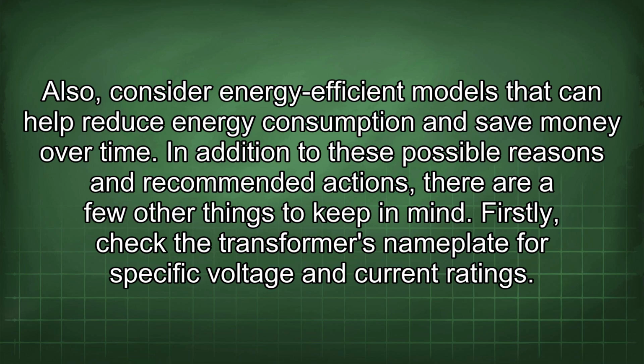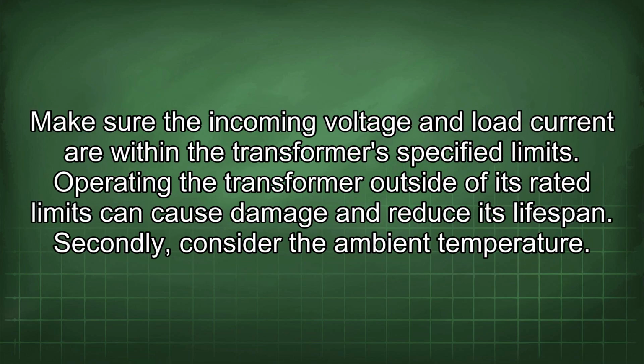In addition to these possible reasons and recommended actions, there are a few other things to keep in mind. Firstly, check the transformer's nameplate for specific voltage and current ratings. Make sure the incoming voltage and load current are within the transformer's specified limits. Operating the transformer outside of its rated limits can cause damage and reduce its lifespan.